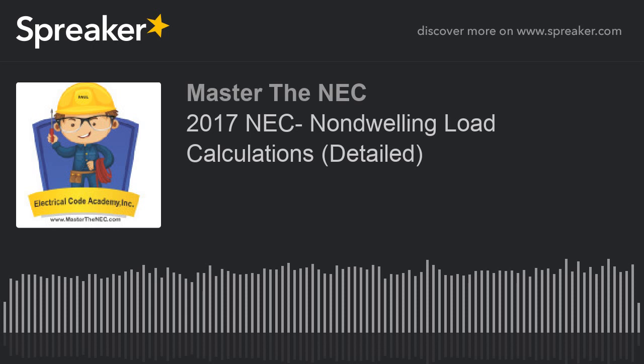So you need to define in a building whether the loads we're talking about are continuous or non-continuous, okay? Any lighting that's going to be on for 3 hours or more is going to be a continuous load. So just things to consider as we're moving through this. And you see that the list is very limited. Now, obviously, we're not going to talk dwelling units because we've already done that ad nauseam in other podcasts and videos. So we're going to go down the list. Now, we did a bank and a store. They're not listed here, so they would fall down under the list where it says all others. And you see it's 100%. So we have to take the values at 100%.